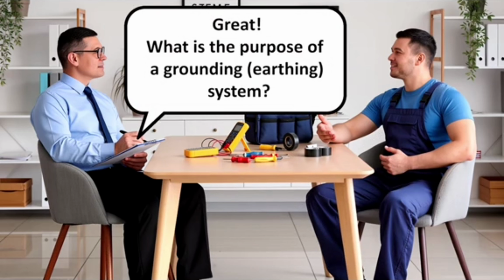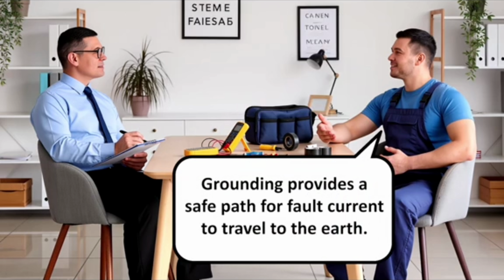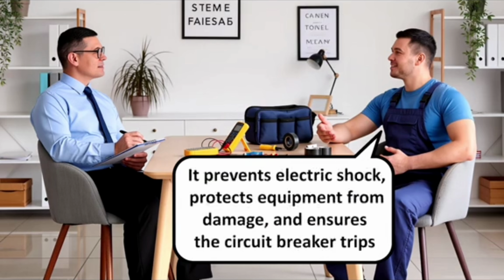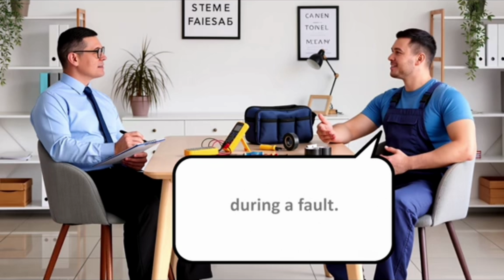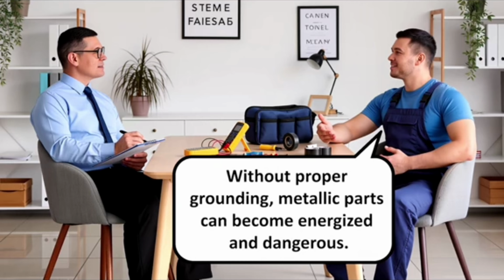Great. What is the purpose of a grounding or earthing system? Grounding provides a safe path for fault current to travel to the earth. It prevents electric shock, protects equipment from damage, and ensures the circuit breaker trips during a fault. Without proper grounding, metallic parts can become energized and dangerous.